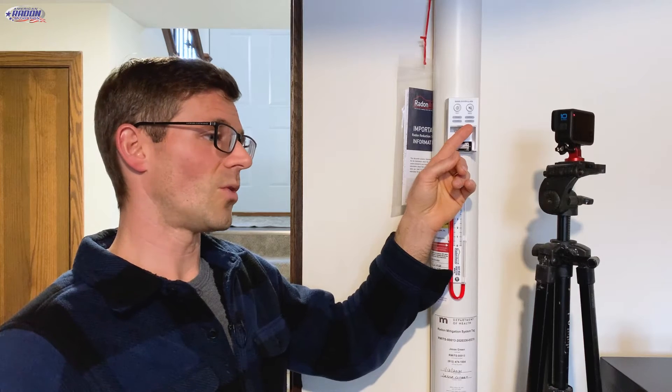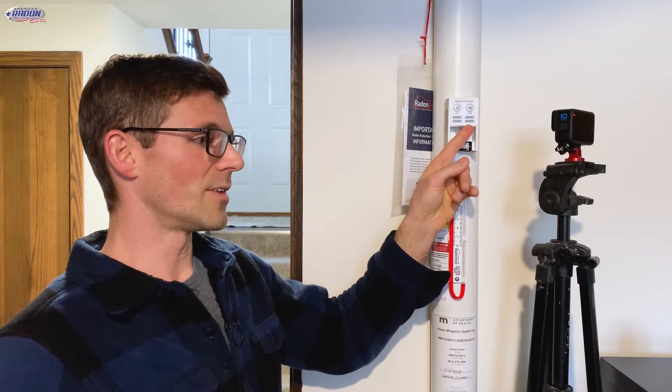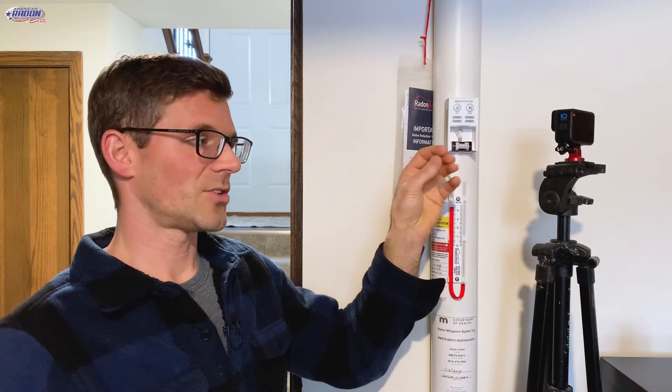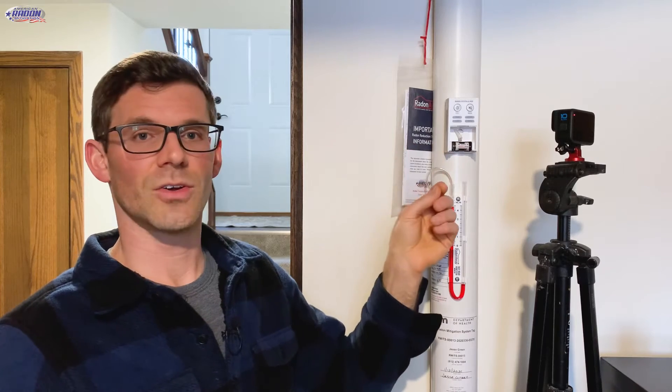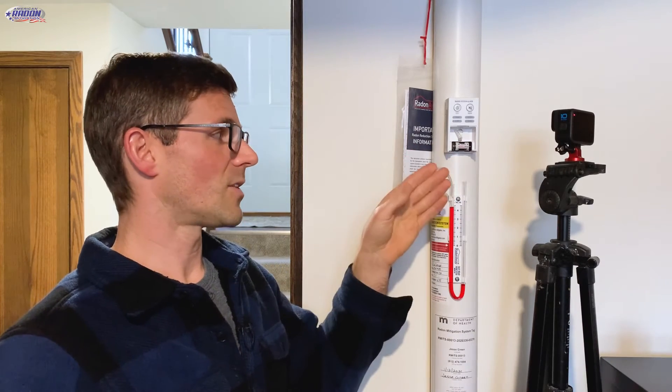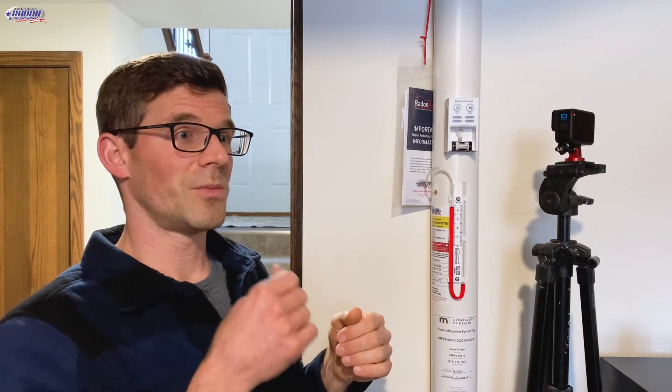So what happens in service mode is this blue light is going to come on and flash every 60 seconds, and you're going to hear a beep. And then that's telling you that you've got some sort of problem. It could be the system's frozen. Maybe that breaker that that fan is on has tripped or somebody shut it off or somebody unplugged it for some reason.